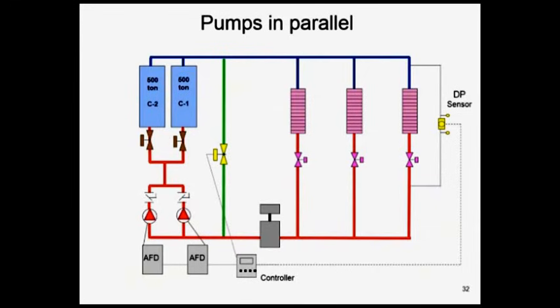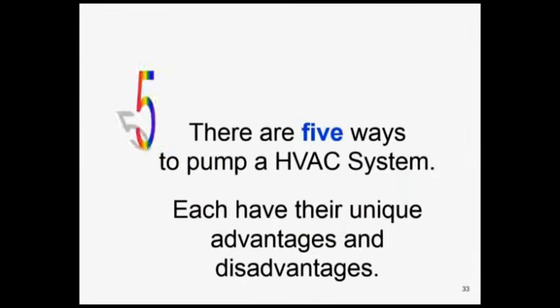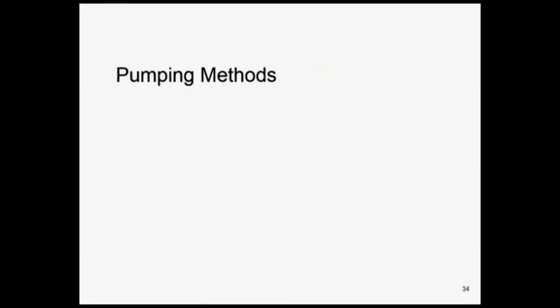And you see these pumps again are pumping through the chillers and our boilers all the way out to the distribution pipe and to the very end. Again, make that simple system sketch if you're going to balance these so you understand. So if I summarize, and this is very important if you're going to be in the balancing business, you should be able to recognize these 5 basic systems and make a sketch before you set out to balance the job and know what GPM you need at each building and understand why.